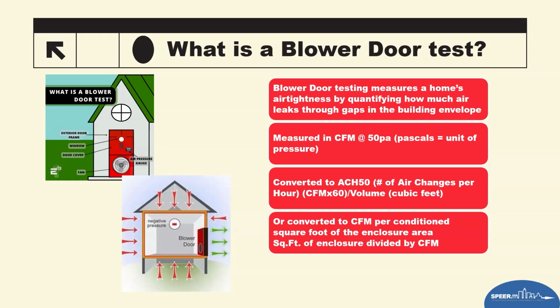Once the CFM is measured, it must be converted to be useful for us. Just looking at it and saying, well, my CFM was 2,438, that doesn't really tell me anything. You can have the manometer set up and tell you in square inches what size that hole is, roughly estimating how much leaking is going through the building. But again, it doesn't point out where.